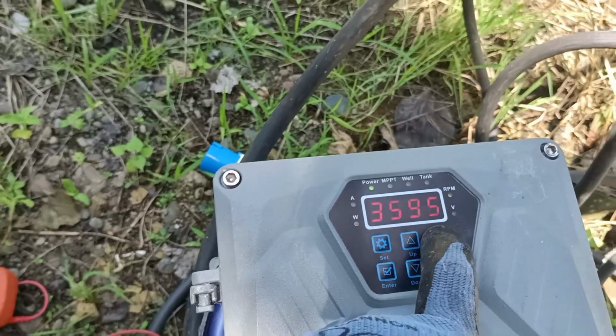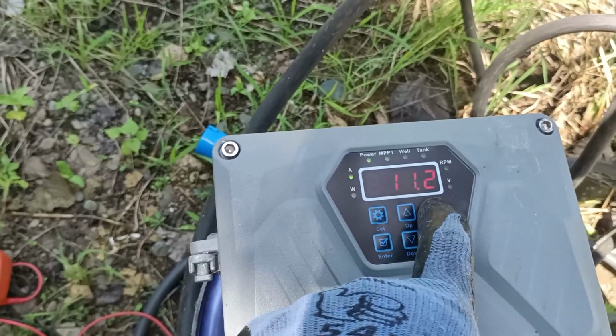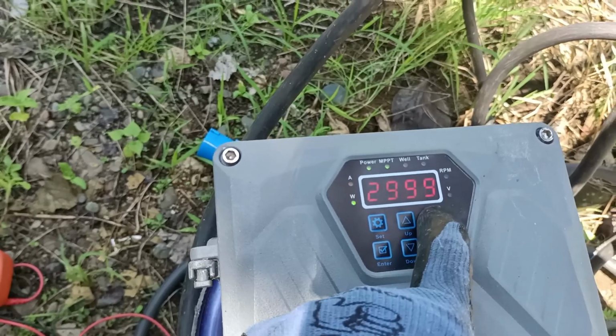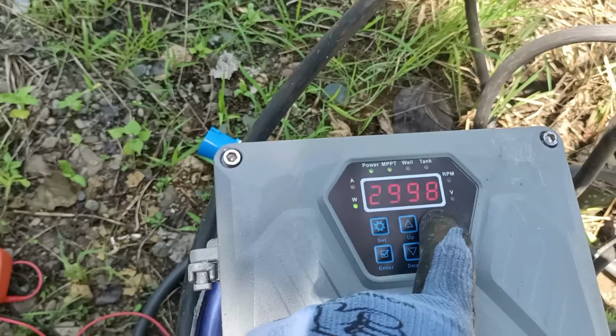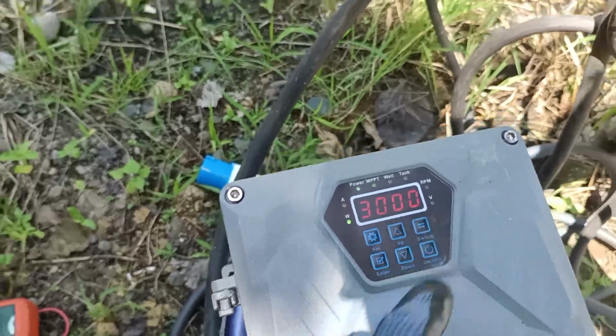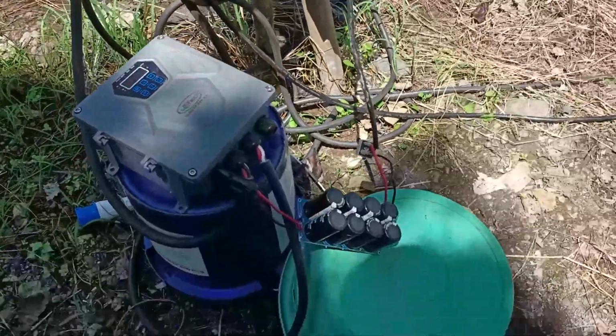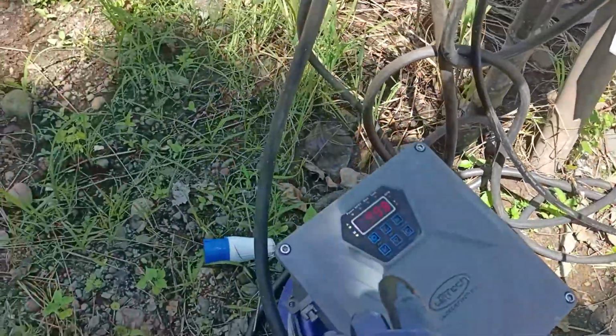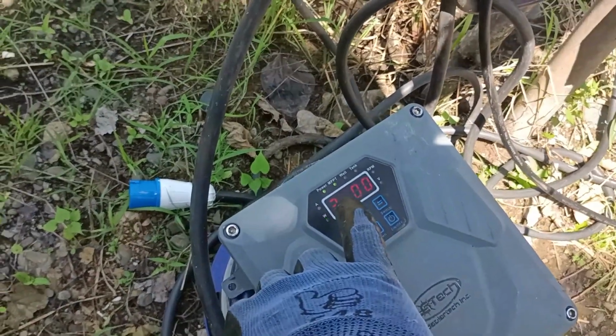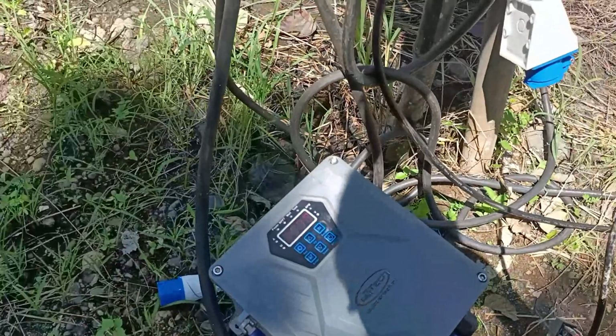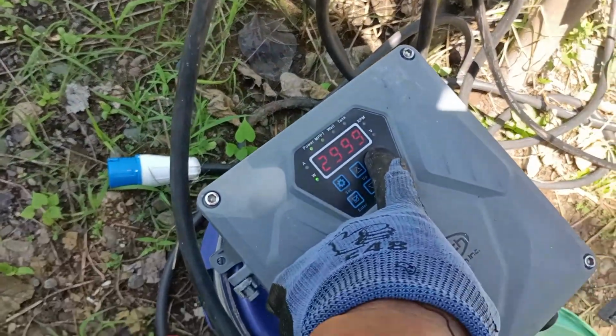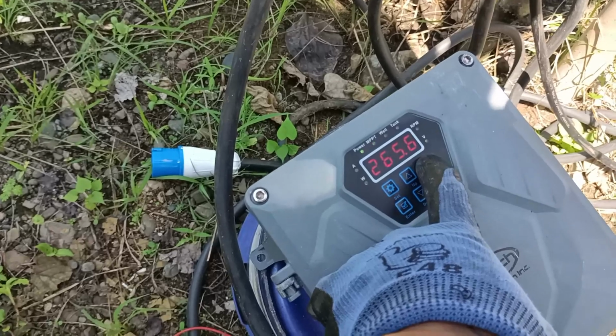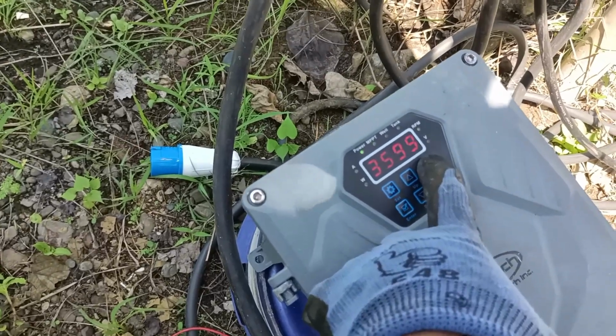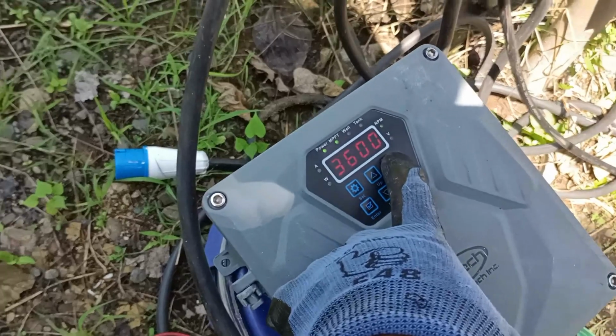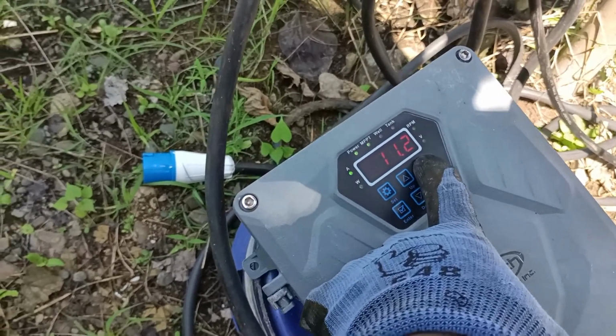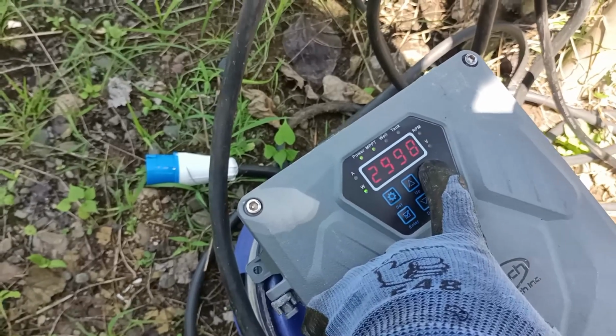And then RPM is, let's just say 3600, 11.2 amps, it's a 3000 watt max, so this is what it's rated for. And it's actually using MPPT, so it's looking at the voltage, adjusting the RPM according to voltage, and it also looks at the amps. So it says, oh, I can set it up at 3500 or 3600 RPM, 11 amps, so it's actually running at max.